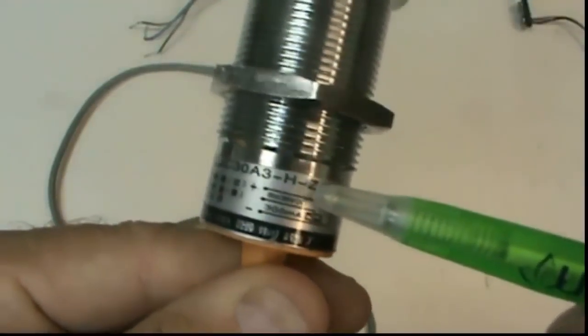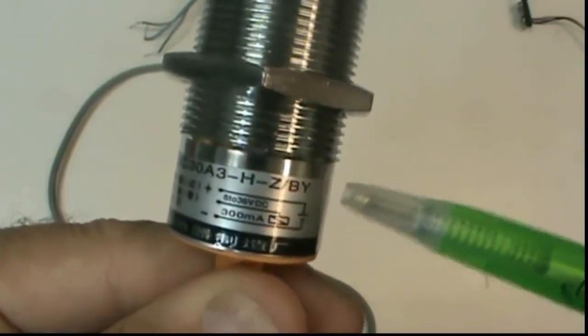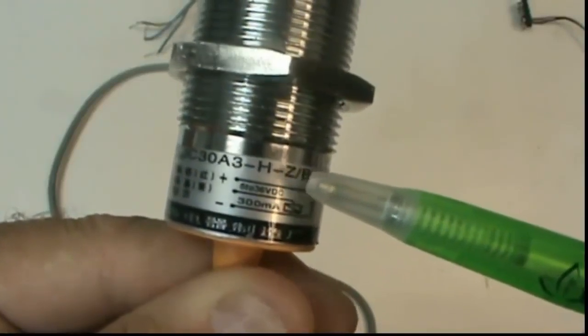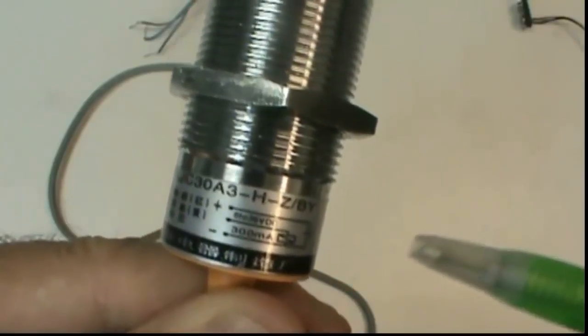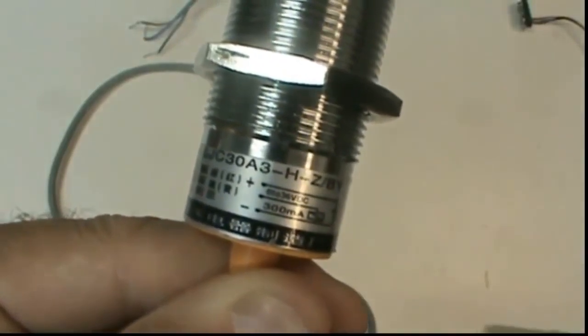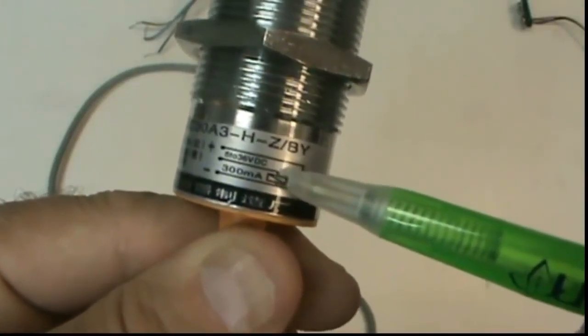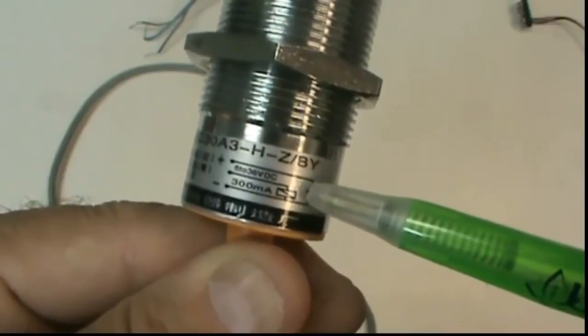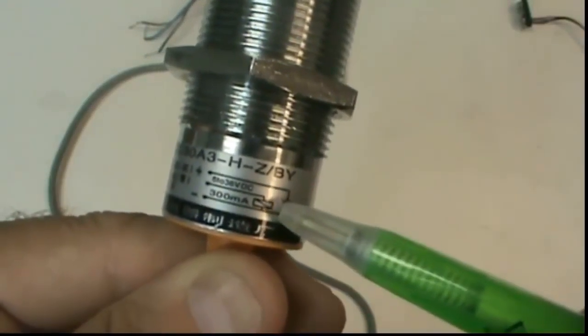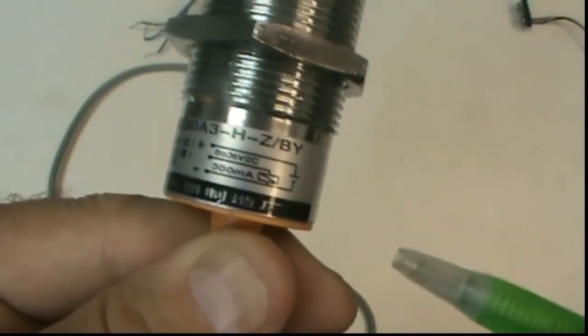There's a little diagram here that shows you how to hook it up. You apply your positive voltage to the positive input of the sensor, and your load, or the thing that the sensor is going to be hooked to, could be a sinking input, is the little symbol there, the square symbol with a slash through it, and then your negative goes to the bottom terminal of the sensor.